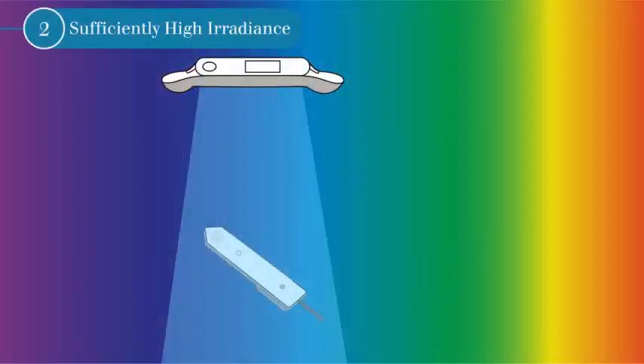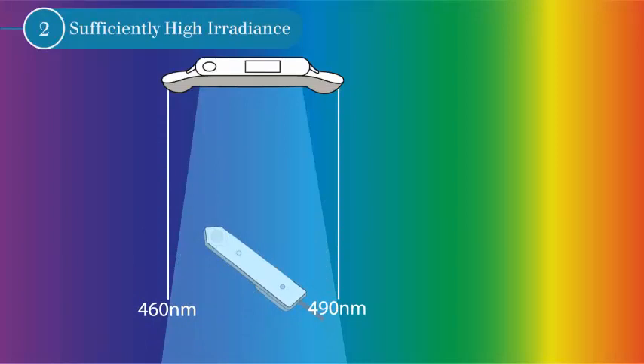Applying this to light irradiance, it's advisable to use a radiometer covering the exact light spectrum that's beneficial to treat hyperbilirubinemia.